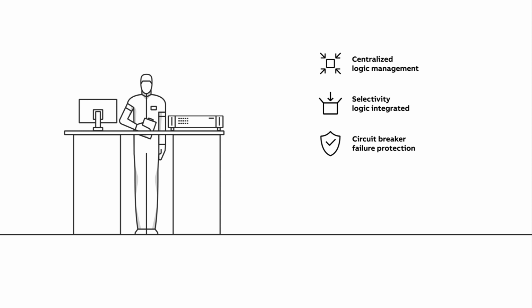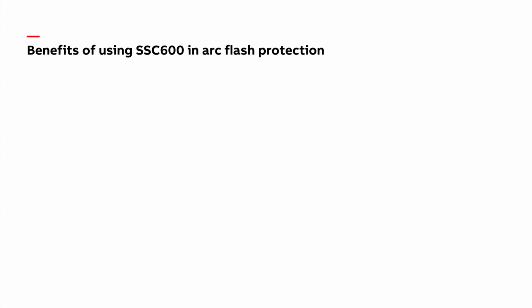With SSC600, you can also have redundant communication to further improve the reliability of the communication system in this critical arc flash protection application. In a substation-wide arc flash protection scheme, with light and current conditions, an SSC600 base system has the same protection speed level as conventional arc protection solutions. This is achieved thanks to IEC 61850 based communication. There are many benefits of using SSC600 in arc flash protection application.